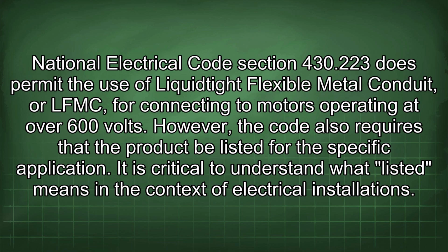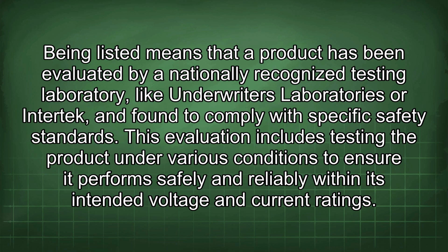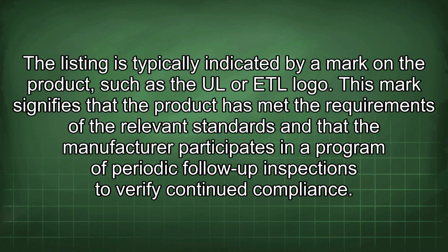It is critical to understand what listed means in the context of electrical installations. Being listed means that a product has been evaluated by a nationally recognized testing laboratory, like Underwriters Laboratories or Intertek, and found to comply with specific safety standards. This evaluation includes testing the product under various conditions to ensure it performs safely and reliably within its intended voltage and current ratings. The listing is typically indicated by a mark on the product, such as the UL or ETL logo. This mark signifies that the product has met the requirements of the relevant standards and that the manufacturer participates in a program of periodic follow-up inspections to verify continued compliance.